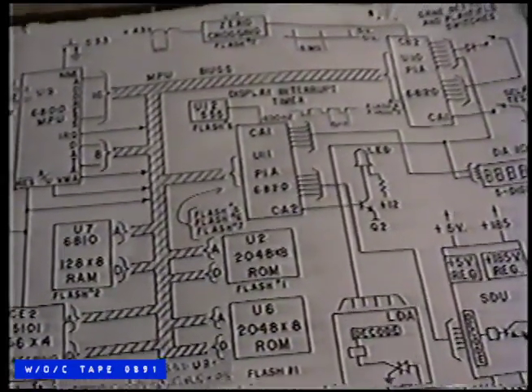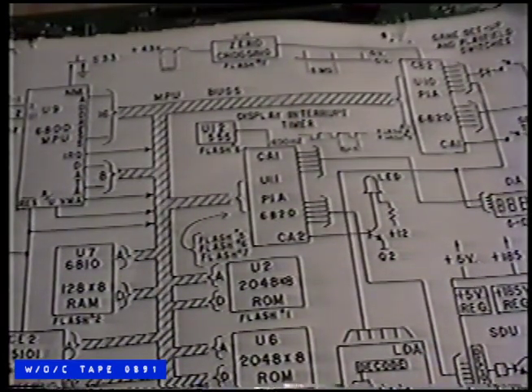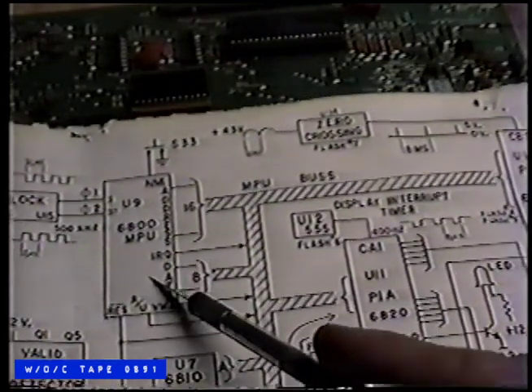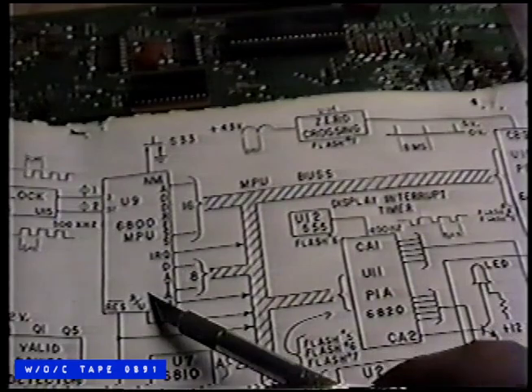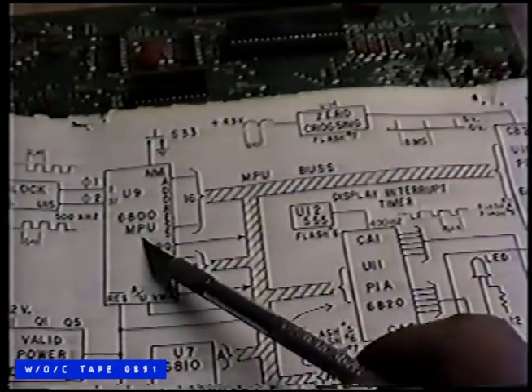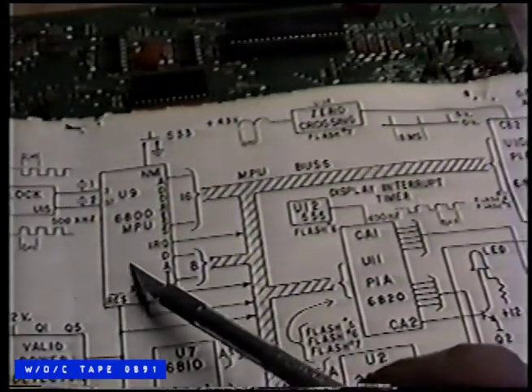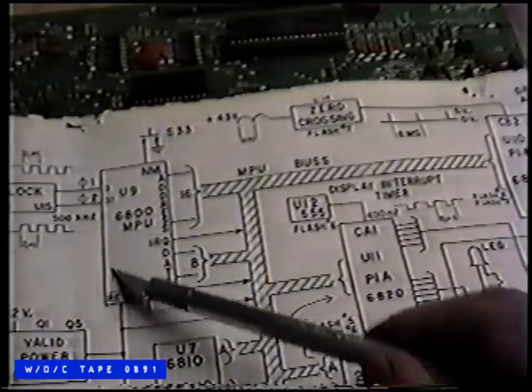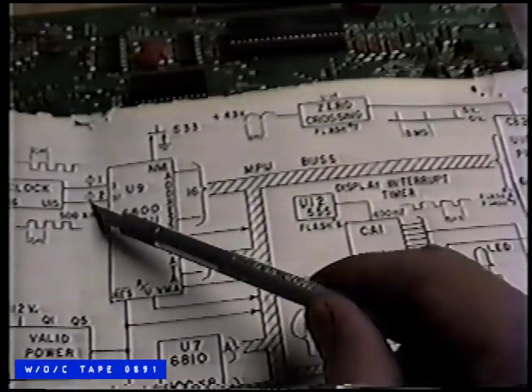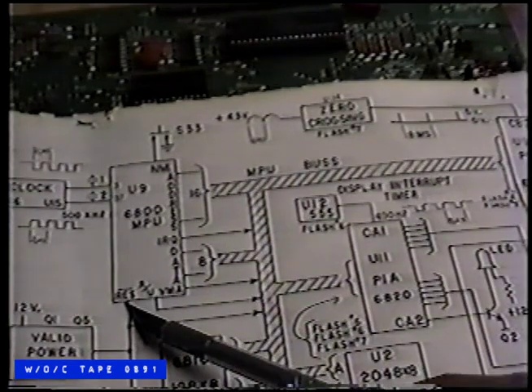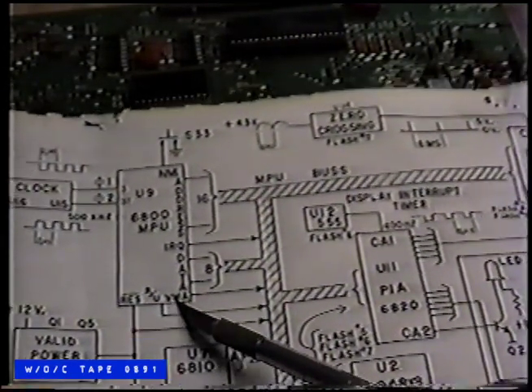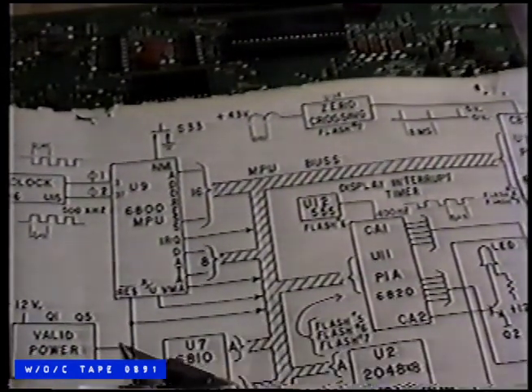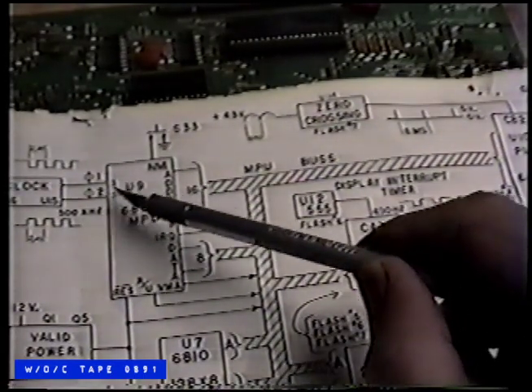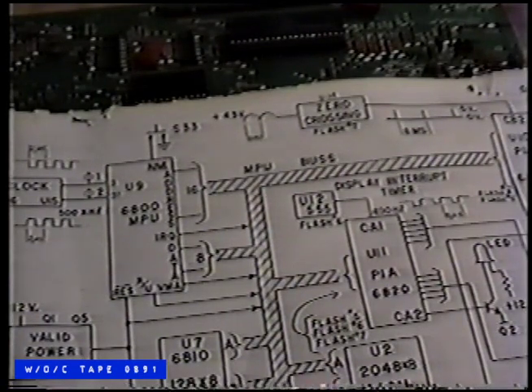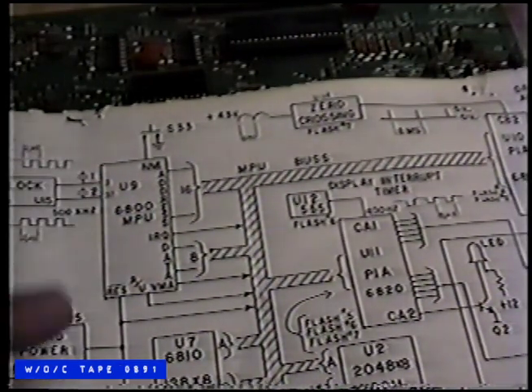Now we'll start with the processor right up here. What they're trying to tell you is that this first flicker is your 6800 MPU, and that first little flicker runs a bunch of tests in and around this particular processor chip. You've got 2 clocks, address, reset, VMA—valid memory address—interrupt request, data lines, and read and write. All of this has to be up and running, or it won't even do that little flicker. If it just comes on and stays on without the flicker, then probably you've got a problem with the processor—but it really could be anything connected to the processor also.